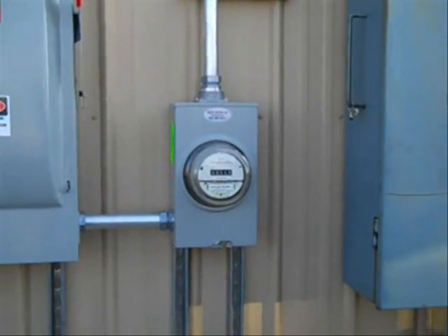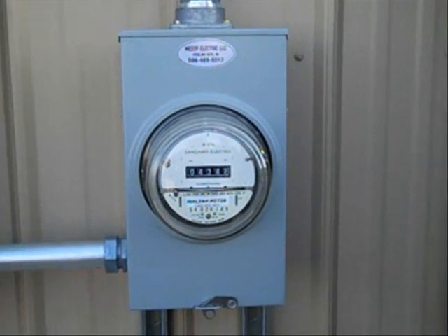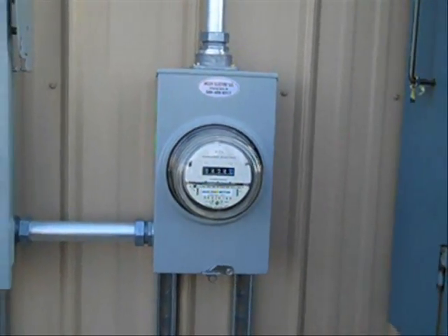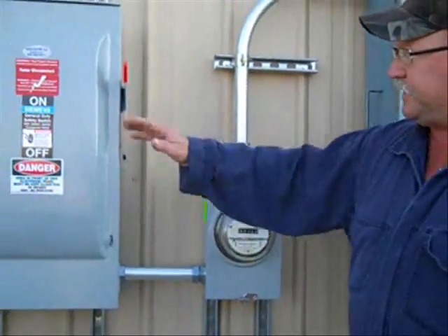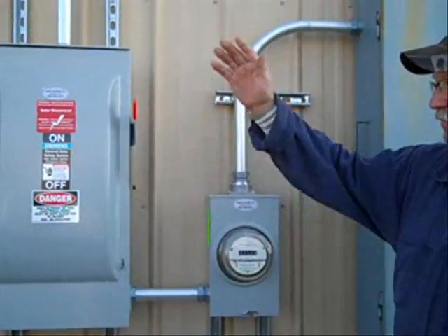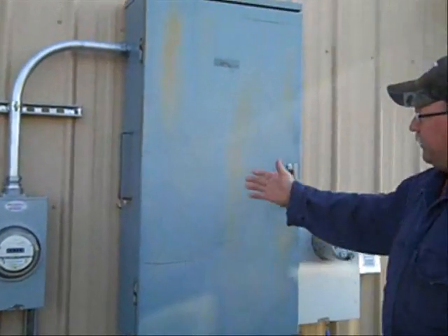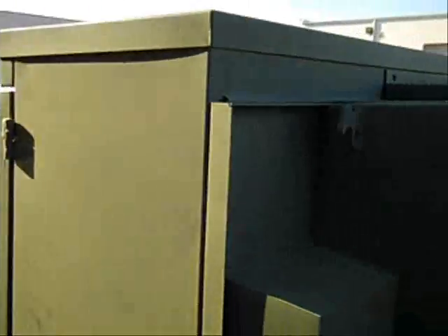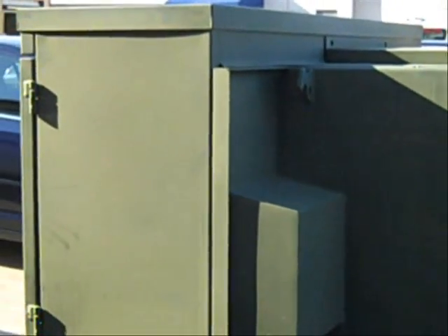As a matter of fact, since we had this going on, we've produced about 800 kilowatt hours, which is pretty awesome. You can see the meter's going pretty quick here. This is hooked up and running right now. And this is the path we take when we backfeed it into the system. We come from the inverters to that combiner panel to the system disconnect to the meter, and then we pump it back into the CT cabinet that's actually fed behind Dave here into this transformer right here. And then that's the circle of electricity back into Detroit Edison, back into the power lines.